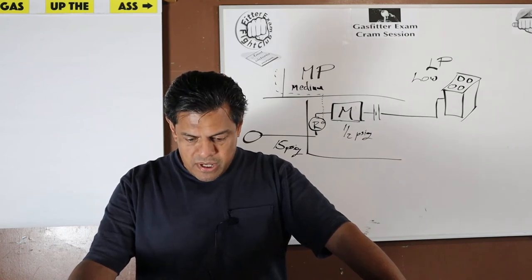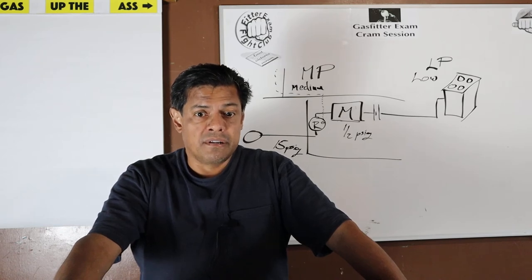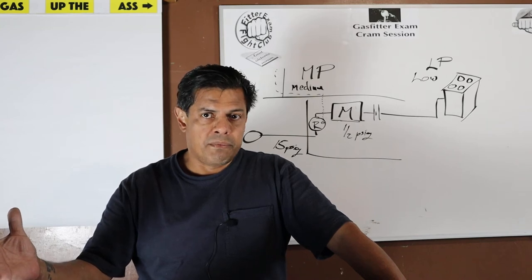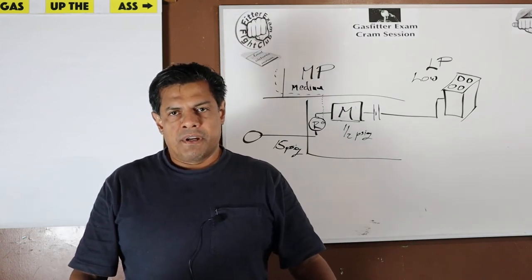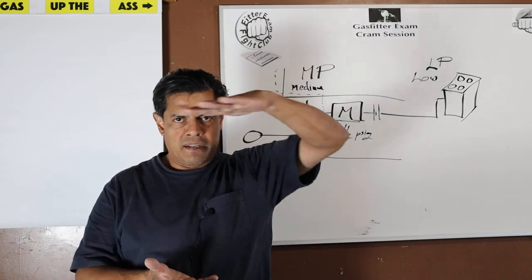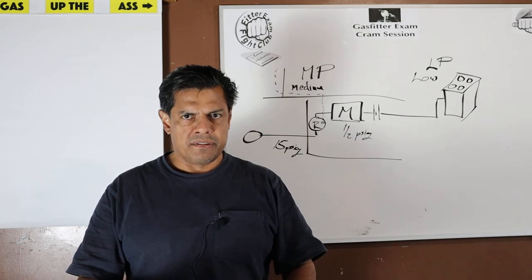All right, so 18 inches above grade. We're going into other codes, but just to show you how prevalent this number can be and why we start getting obsessed with numbers, giving them these magical powers that they really don't have. Well, because it helps us remember it, okay? Let's see, the fire department connection or the Siamese has to be at least 18 inches above grade. When you have it outside the wall, or if it's freestanding, it's got to be 18 inches above grade, right? If we're going outside and we're talking about grade, it's a good chance 18 is going to be the answer.